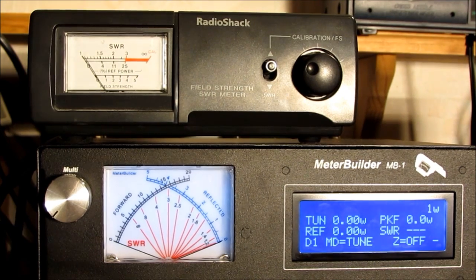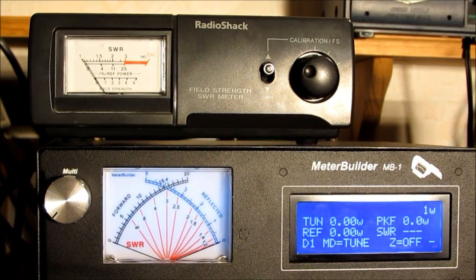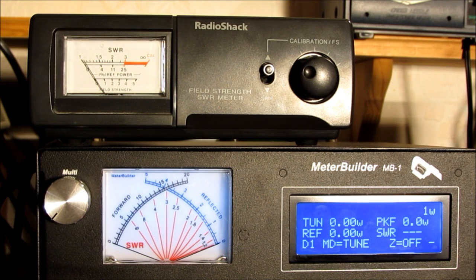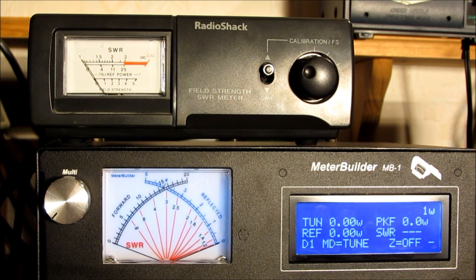MeterBuilder has a unique feature that allows you to calibrate almost any Bird-type coupler using MB-1's coupler calibration algorithm. If you already have an MB-1 and also already have VHF and UHF couplers, you probably can interface them to MB-1, save yourself some money, and achieve a level of accuracy that's limited only by the reference meter you use for the calibration.